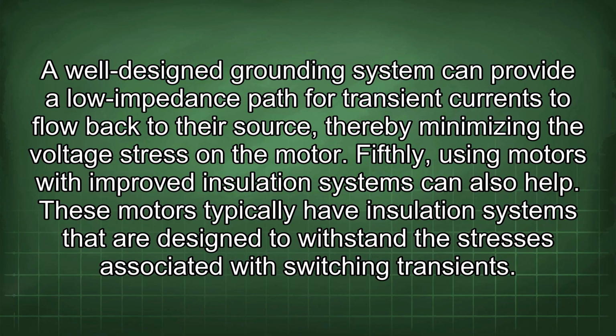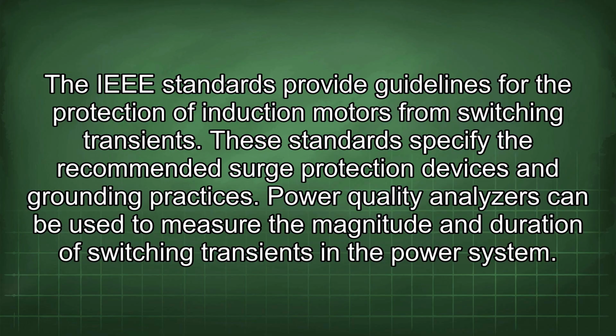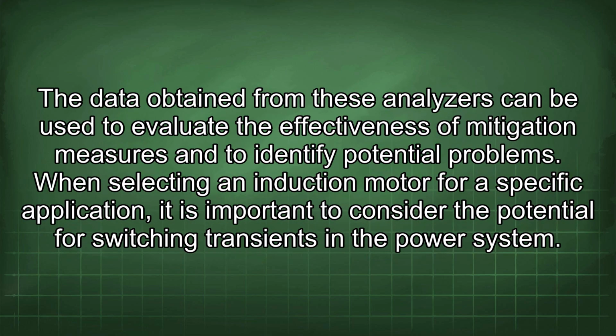Fifthly, using motors with improved insulation systems can also help. These motors typically have insulation systems that are designed to withstand the stresses associated with switching transients. The IEEE standards provide guidelines for the protection of induction motors from switching transients. These standards specify the recommended surge protection devices and grounding practices. Power quality analyzers can be used to measure the magnitude and duration of switching transients in a power system. The data obtained from these analyzers can be used to evaluate the effectiveness of mitigation measures and to identify potential problems.